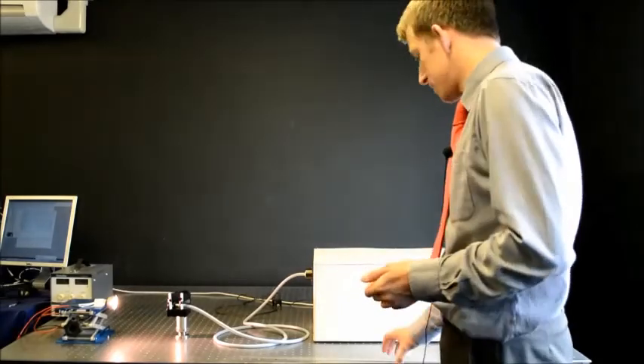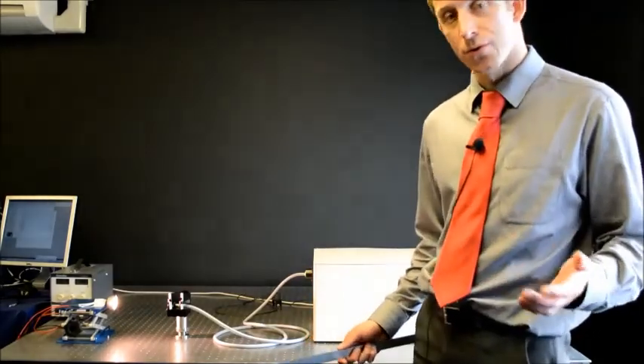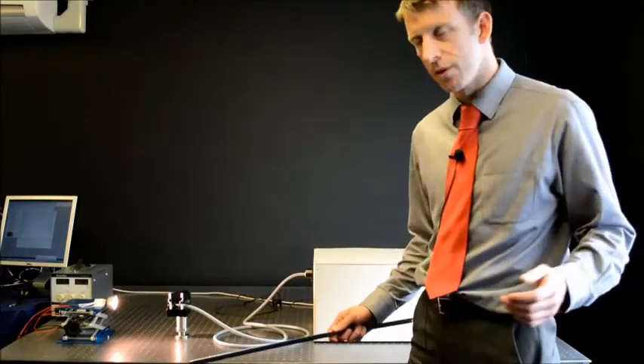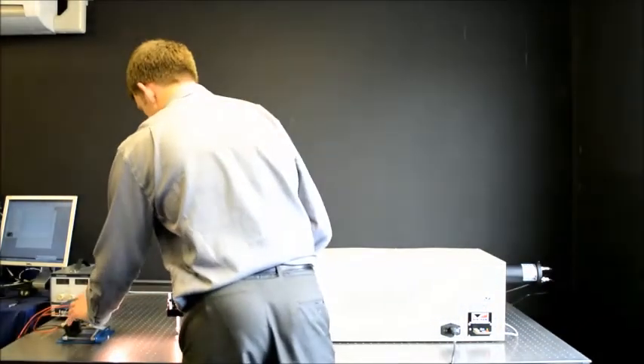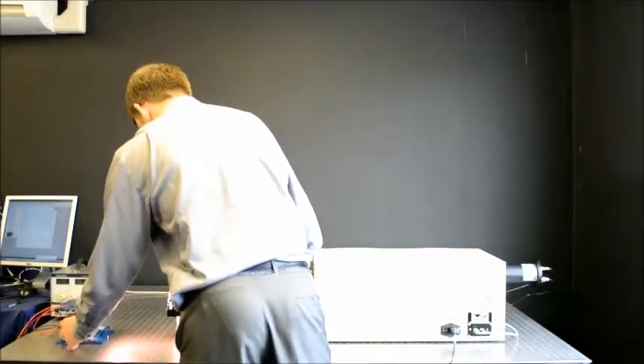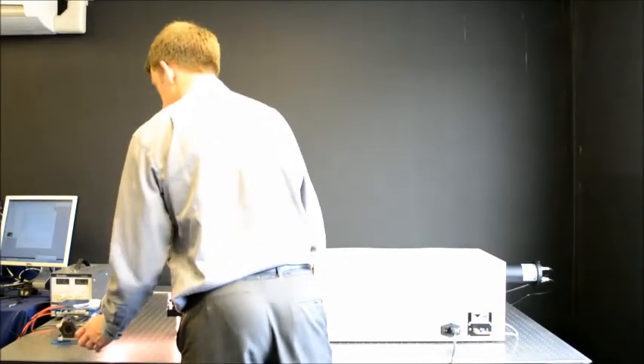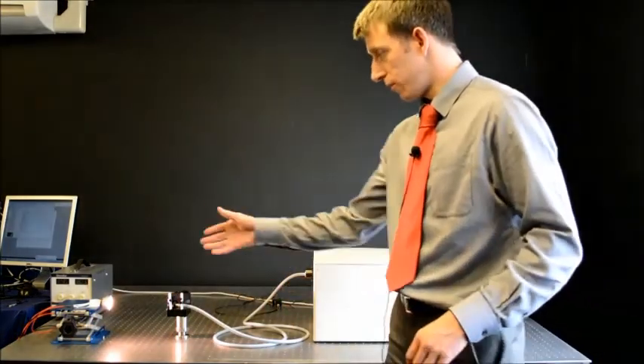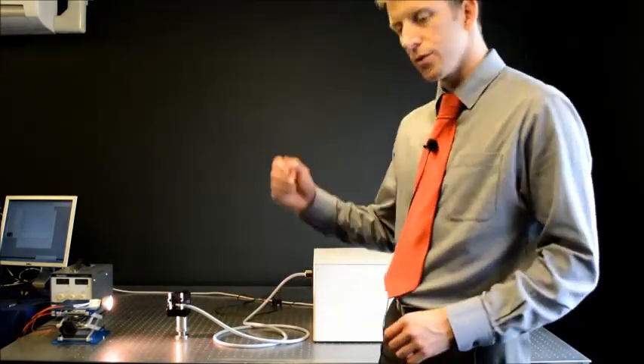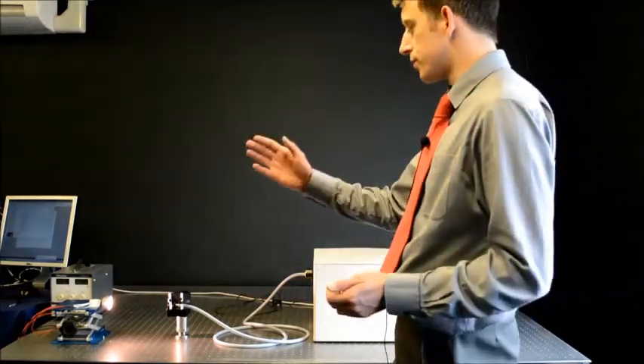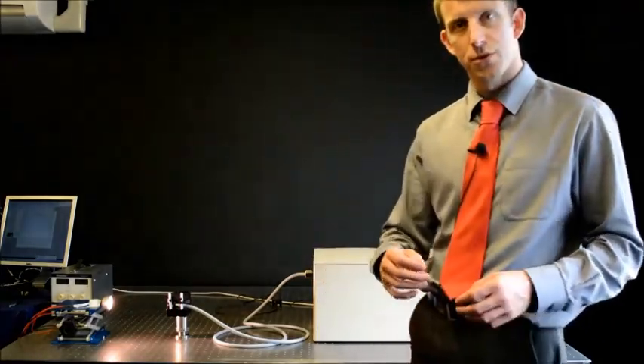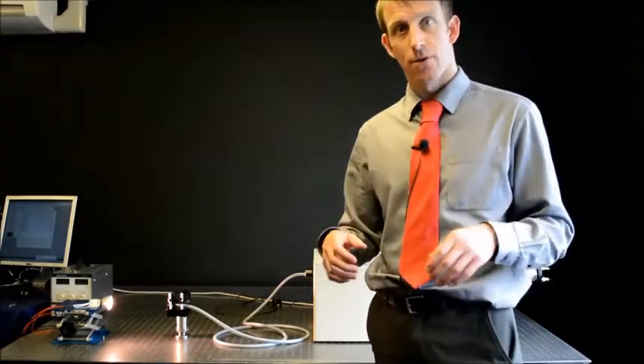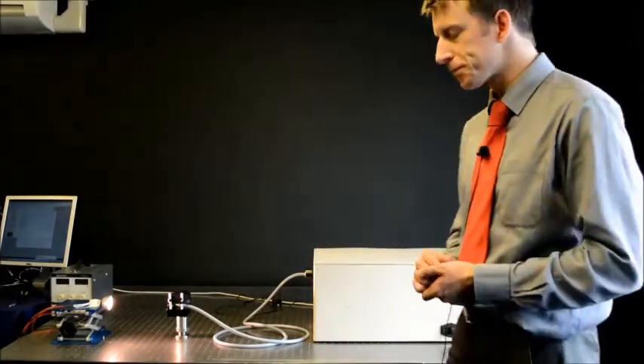The measurement distance should be 200 millimeters from the apparent source location, which for the source we have determined as effectively the front plane, and we can measure 200 millimeters from the front of the diffuser to the front of this source, and use the alignment utility in the software to adjust the lateral and vertical position to obtain a maximum. Here, as opposed to spectral check, we really are concerned with a maximum value because we're now analysing the worst case scenario at 200 millimeters.